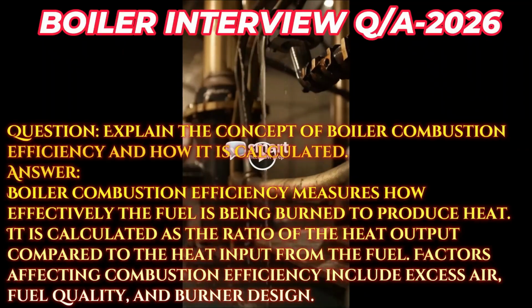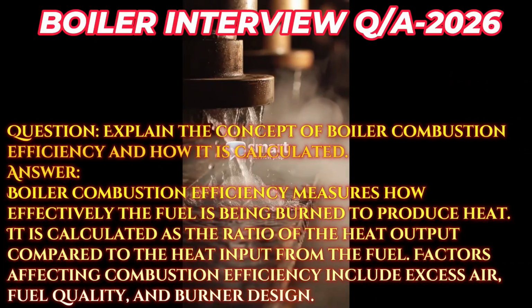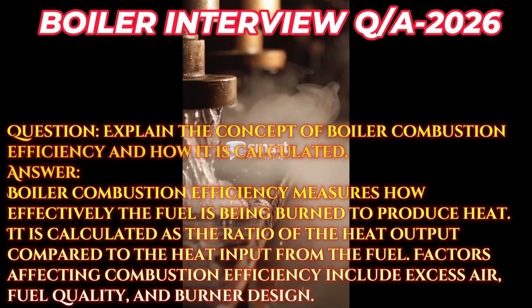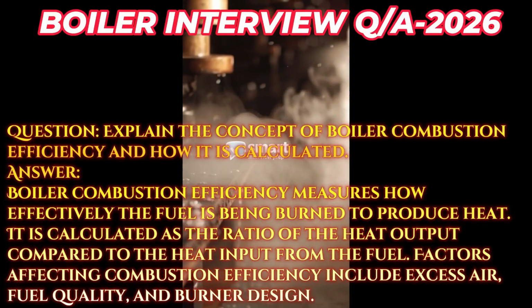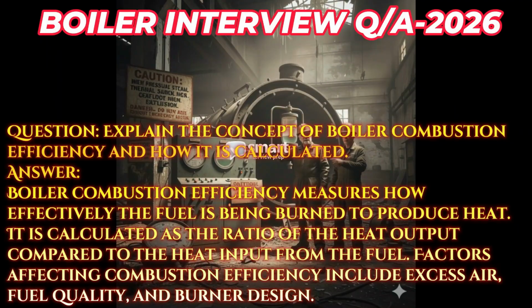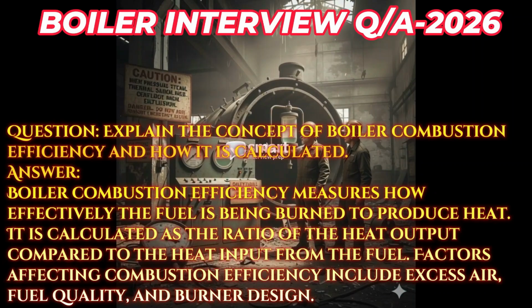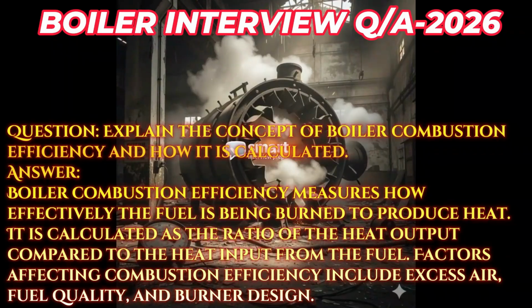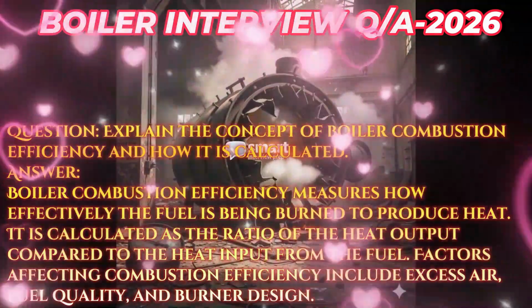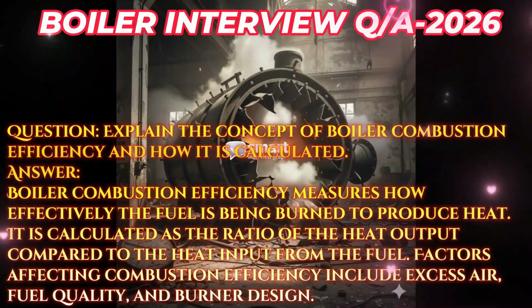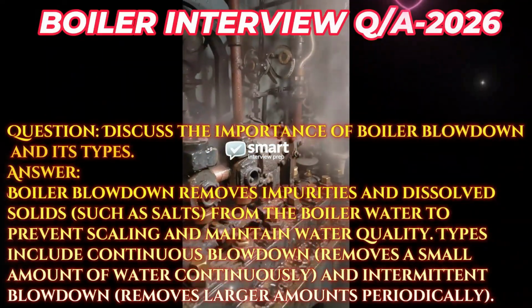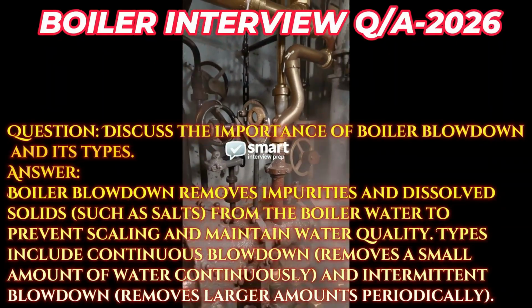Answer: boiler combustion efficiency measures how effectively the fuel is being burned to produce heat. It is calculated as the ratio of the heat output compared to the heat input from the fuel. Factors affecting combustion efficiency include excess air, fuel quality, and burner design. Question: discuss the importance of boiler blowdown and its types.